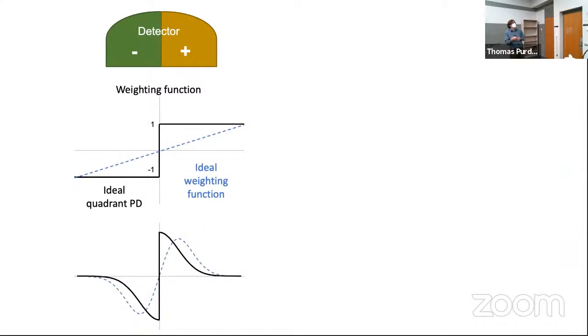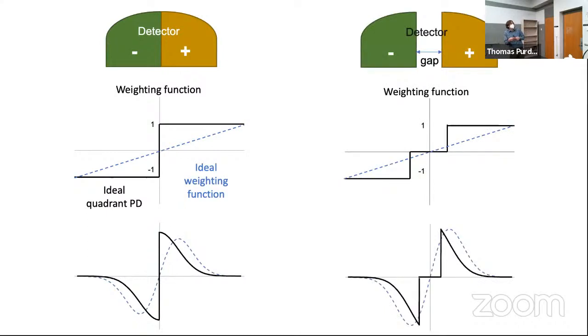We can approximate a linear weighting in a photodetector basically just by sawing our photodetector in half and moving apart the 2 halves, leaving a gap in the middle, or equivalently just blocking out the light in the center. And then this bigger stair-step pattern over on the right approximates the correct weighting function even better. So by effectively throwing away the center half of your laser, not detecting those photons, you actually improve your signal to noise of the quadrant photodetector.